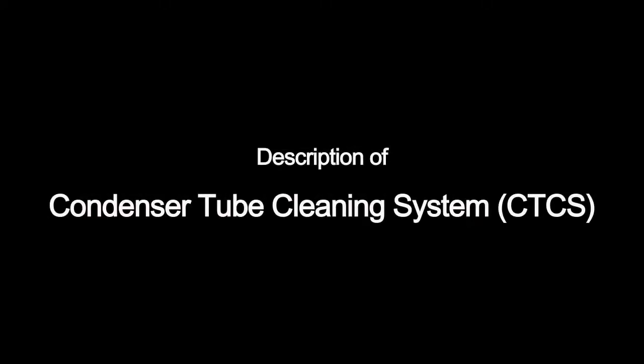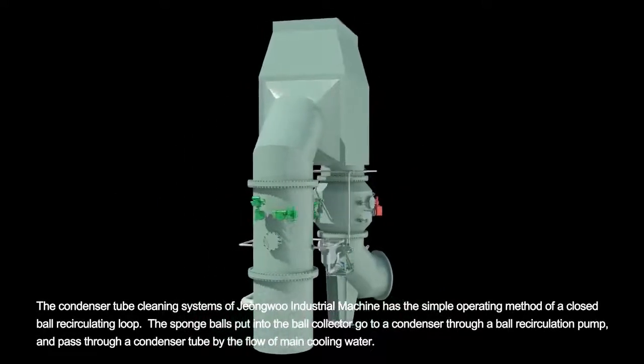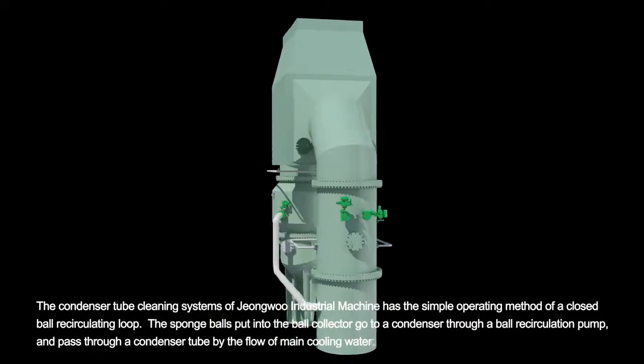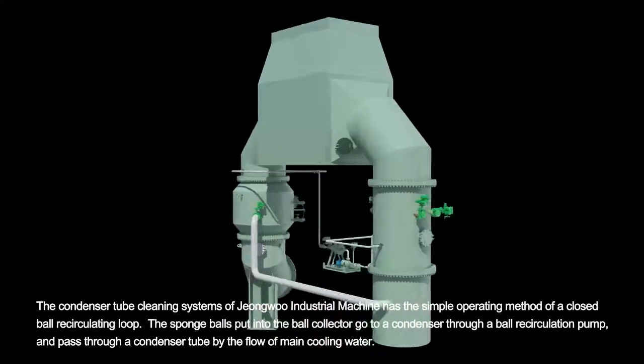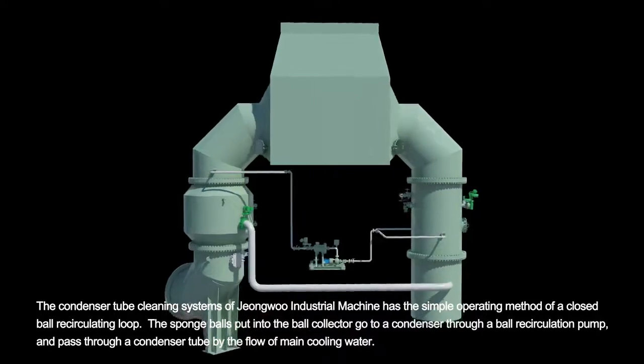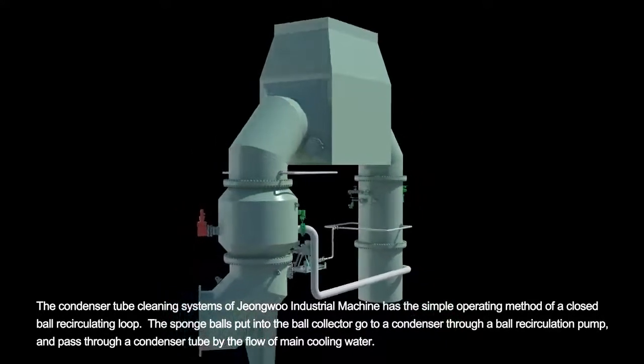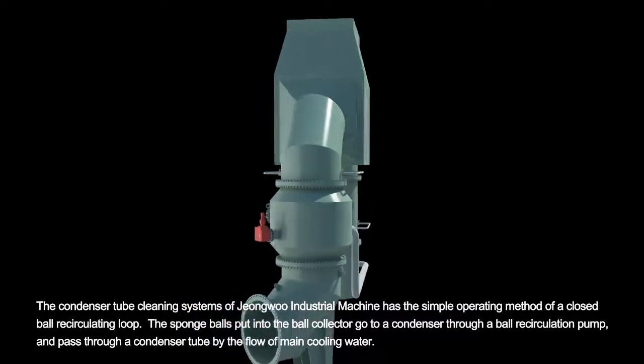Description of Condenser Tube Cleaning System. The condenser tube cleaning systems of Jeongwoo Industrial Machine has the simple operating method of a closed ball recirculating loop. The sponge balls put into the ball collector go to a condenser through a ball recirculation pump and pass through a condenser tube by the flow of main cooling water.